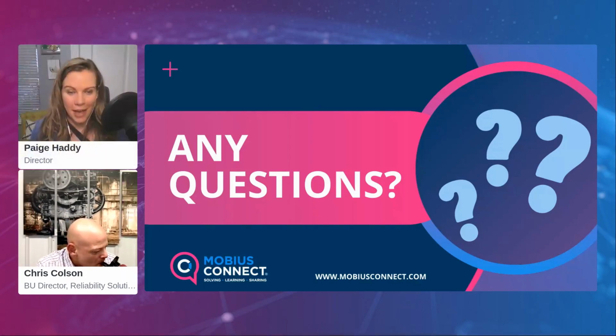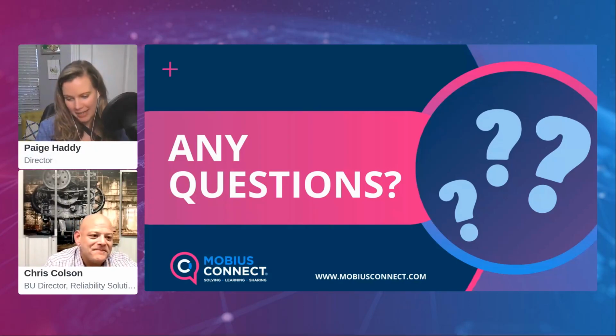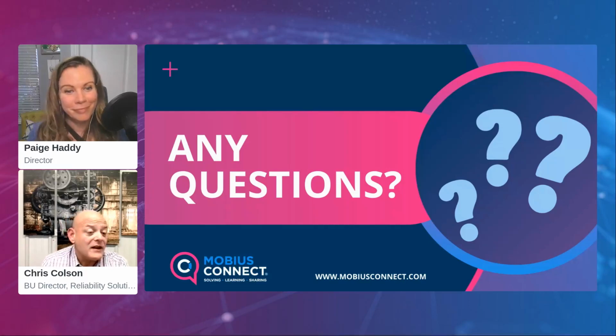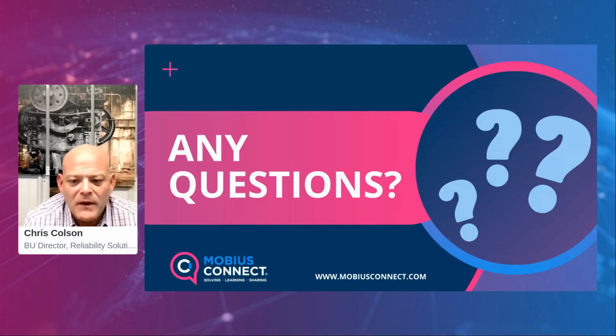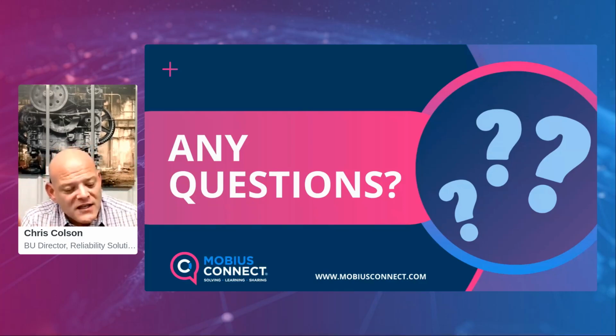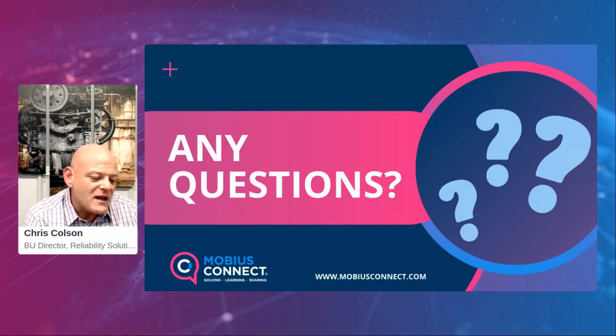So that being said, Chris, our first question asks, how do you prevent work order duplicates in the CMMS when a single condition is persistent in an asset? Yeah, so that's great. I'll tell you what we've done. We have what's in essence called a continued fault entry. In a continued fault entry, we've identified that the defect is still present. And we go back and look, and historically, let's say you were collecting data once every 30 days and nothing got done. A work order was maybe generated, but it was not completed.